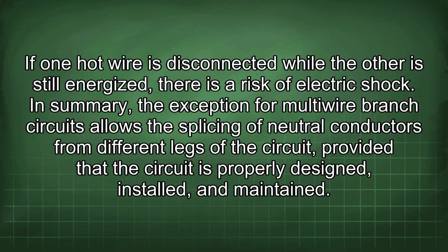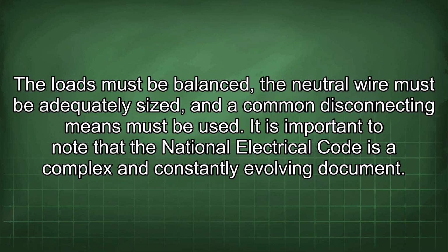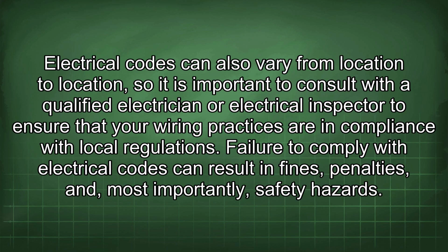In summary, the exception for multi-wire branch circuits allows the splicing of neutral conductors from different legs of the circuit, provided that the circuit is properly designed, installed, and maintained. The loads must be balanced, the neutral wire must be adequately sized, and a common disconnecting means must be used. It is important to note that the National Electrical Code is a complex and constantly evolving document. Electrical codes can also vary from location to location, so it is important to consult with a qualified electrician or electrical inspector to ensure that your wiring practices are in compliance with local regulations. Failure to comply with electrical codes can result in fines, penalties, and, most importantly, safety hazards.